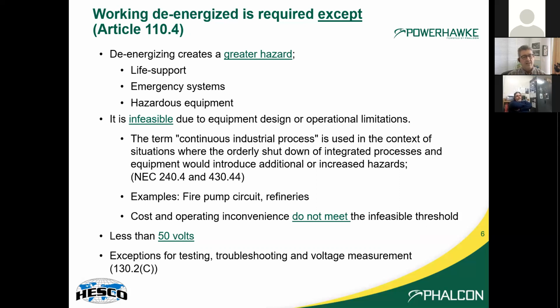One exception, at the very bottom, has to do with that main caveat: this applies to qualified individuals. Qualified individuals can do testing, troubleshooting, and voltage measurement as an exception to working de-energized. You really can't do testing, troubleshooting, or voltage measurement if the circuits don't have any power in them, so you need the potential there to measure that. That's really one of the only exceptions.